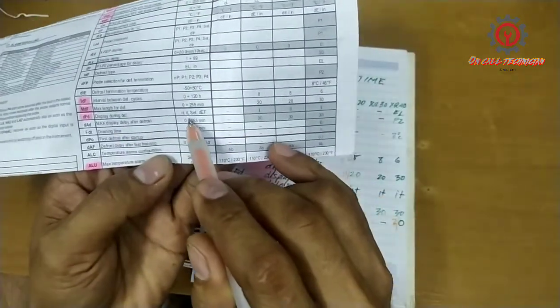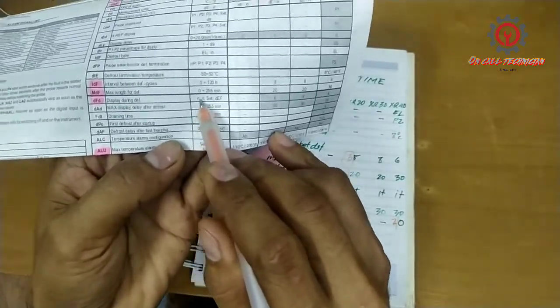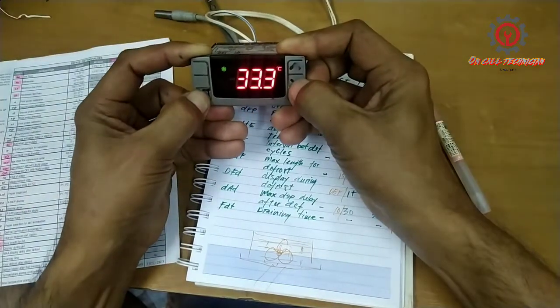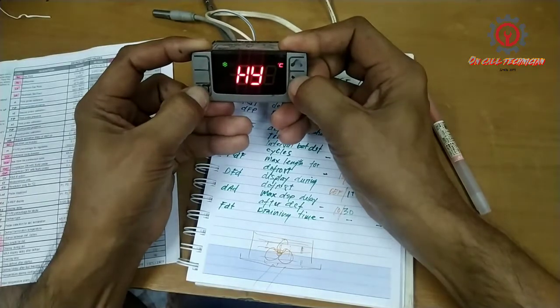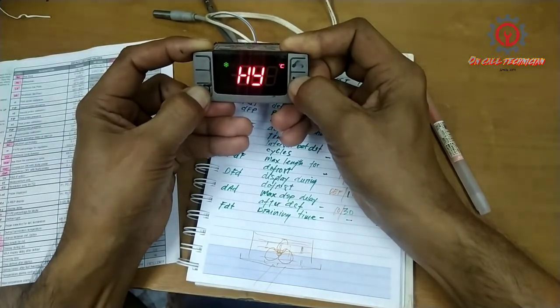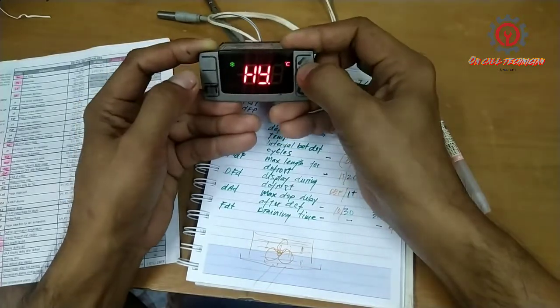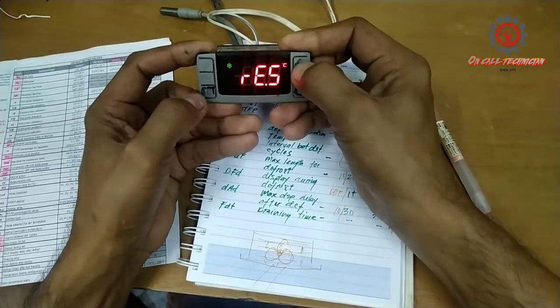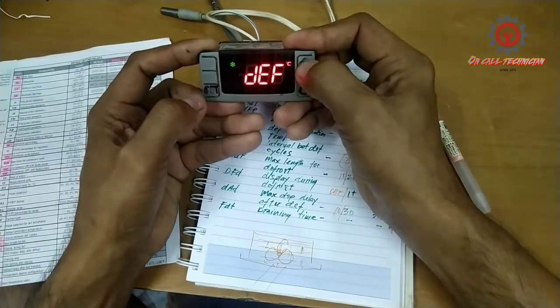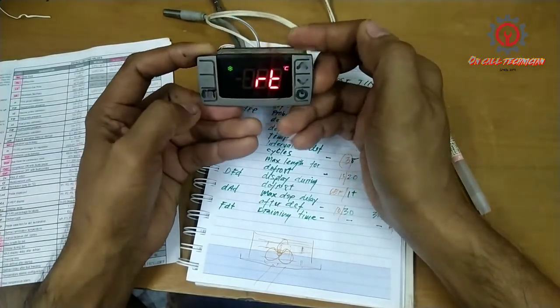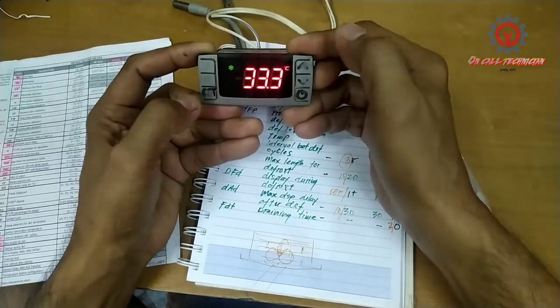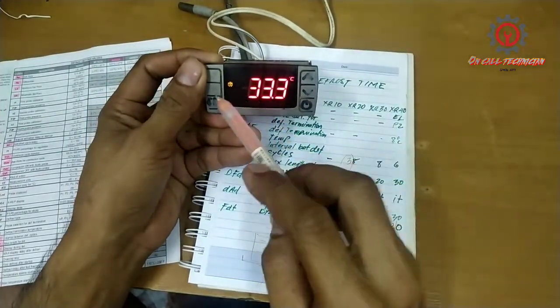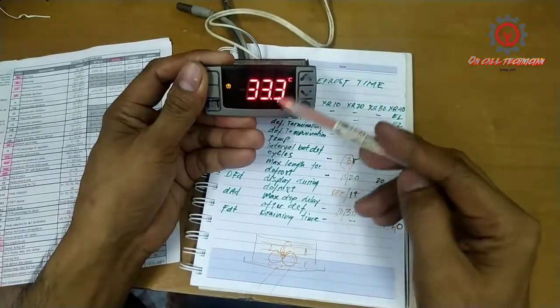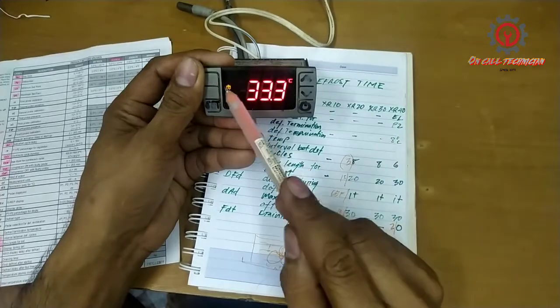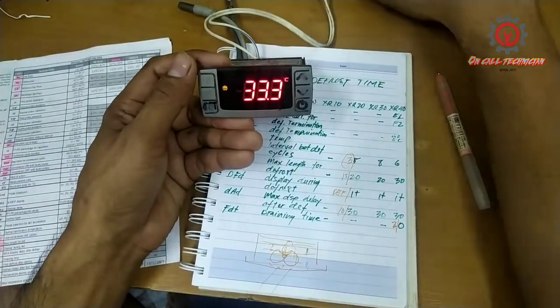And I'm gonna show you again the other types of defrost here. We done for the IT and set, and let's go to RT. Once again, to enter, set button for 3 seconds and 7 seconds. And let's change DFT to RT and set. And let's exit here and defrost. And this is RT. Okay? RT, the display temperature appears, but the defrost symbol lights up, and we're going to reset it again and on again.